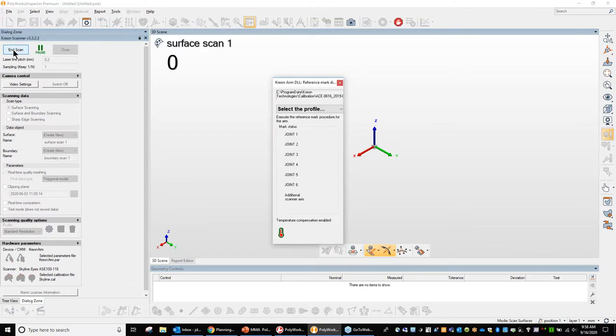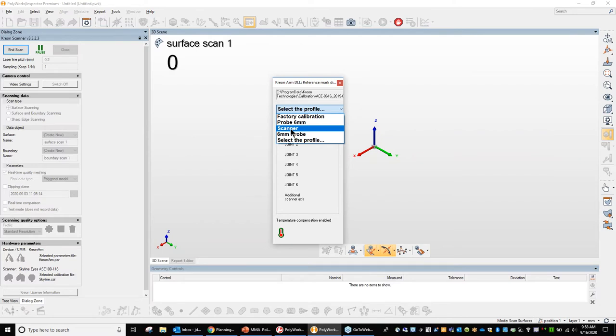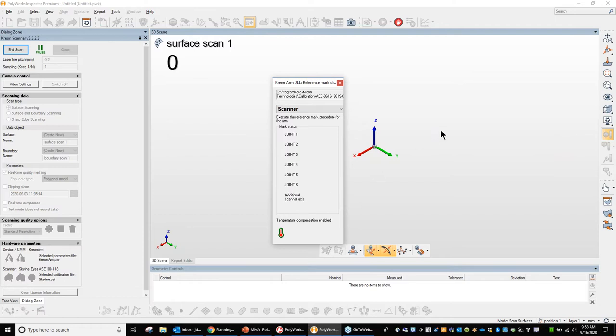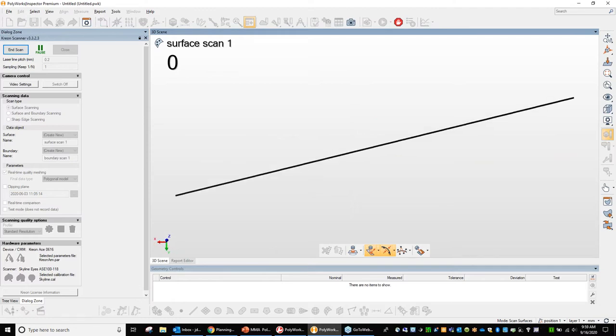Now, because it's the first time connecting to the device with Polyworks here, I must select a profile. And here I have some different profiles. I have just a simple hard probe that I can mount on there. And of course I have the scanner here. So I'm going to select the scanner. That's what I'm going to be showing today. And there you'll see our joints one through six plus your additional scanner axes. That's your seven axis. So here I'm going to go ahead and home the arm by moving the different axes. So you see there's one, here comes the two, the three, the four as I pull it off of the stand. And once that dialogue window goes away, it is now ready to go.